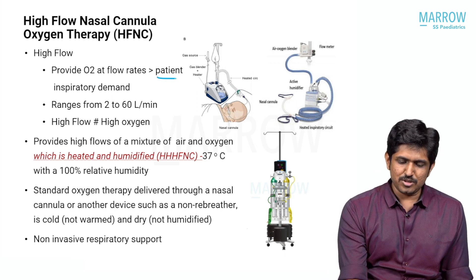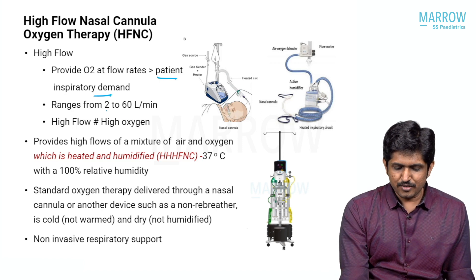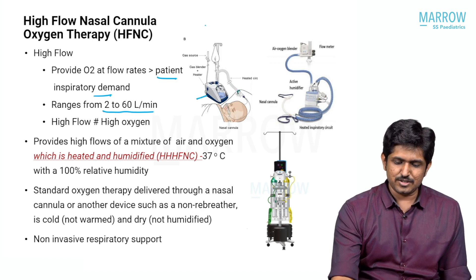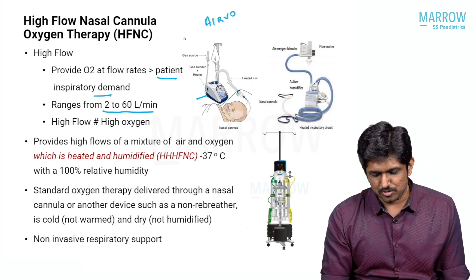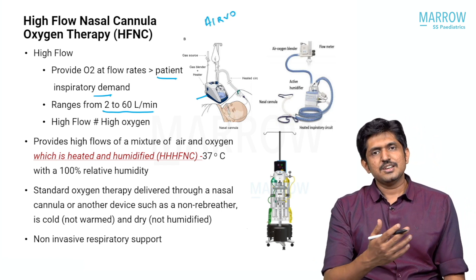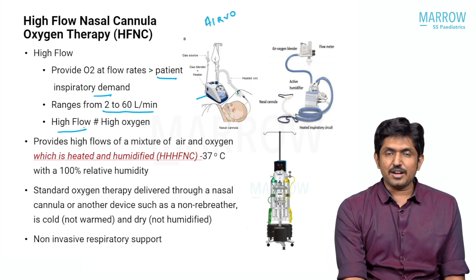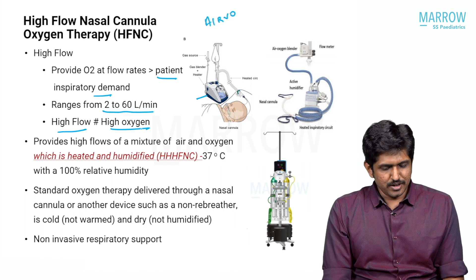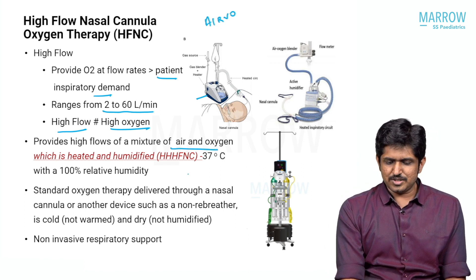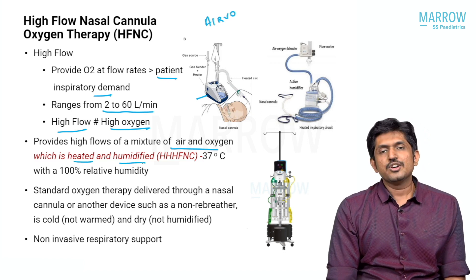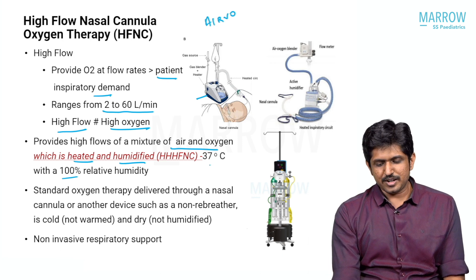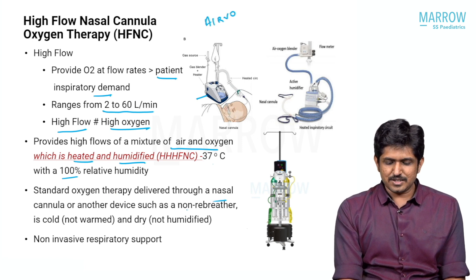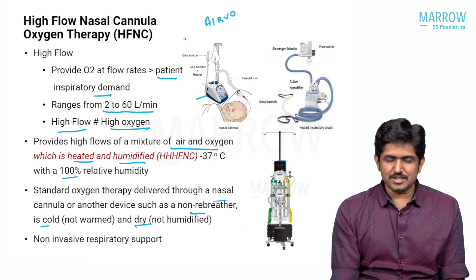Based on this definition, high flow nasal cannula oxygen therapy provides O2 at flow rates more than the patient's inspiratory demand — that is why it is called high flow. The flow range is 2 to 60 liters per minute, delivered by a machine called the AirVO — AirVO 1, 2, and now AirVO 3. You can deliver an FiO2 of up to 90 to 100 percent. It is a mixture of air and oxygen, heated and humidified at 100 percent relative humidity at 37 degrees Celsius, unlike standard oxygen via nasal cannula or non-rebreather mask, which is cold and dry.